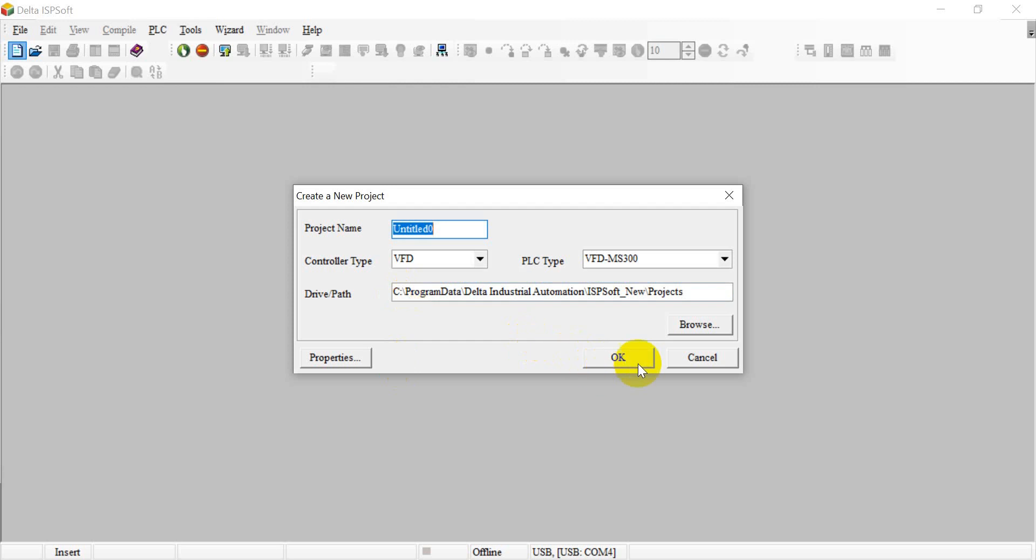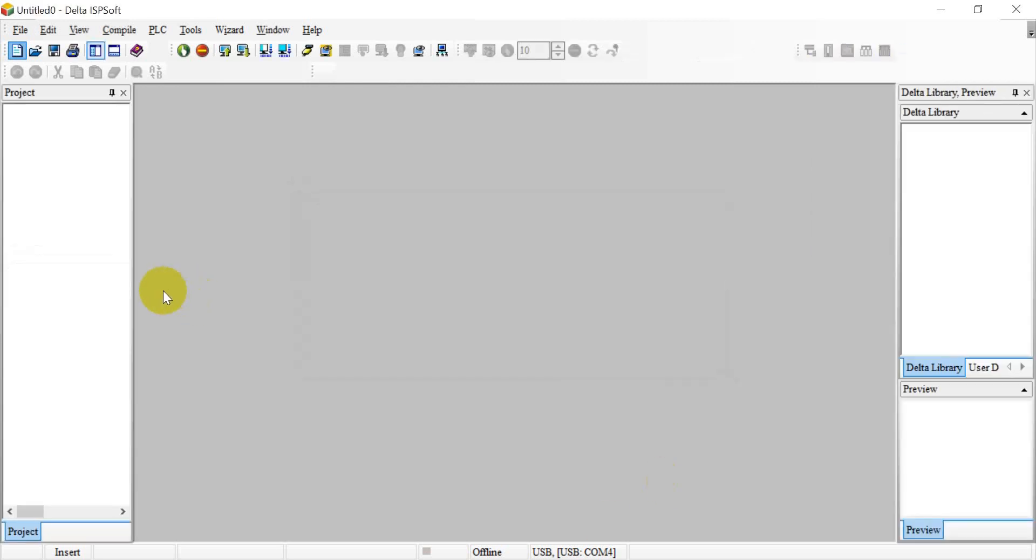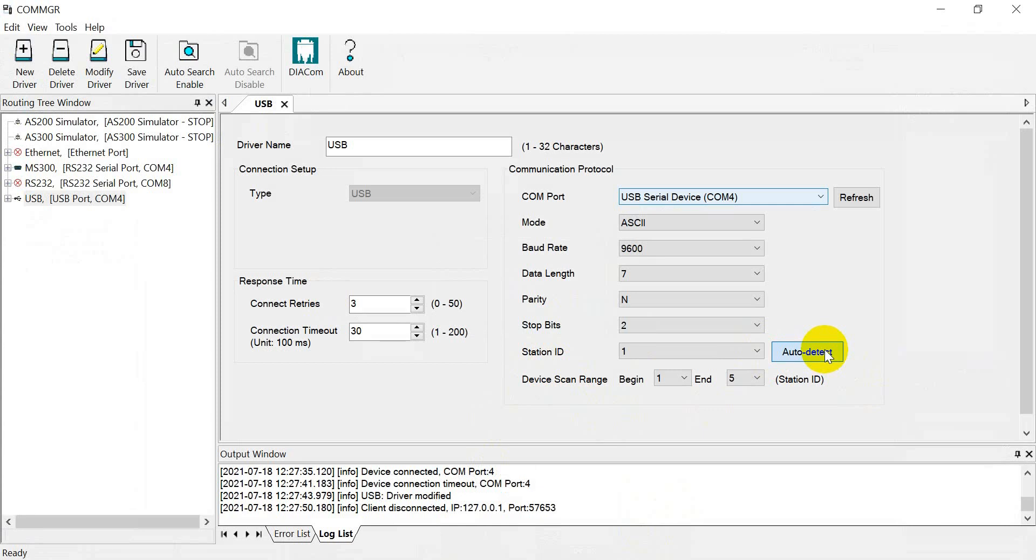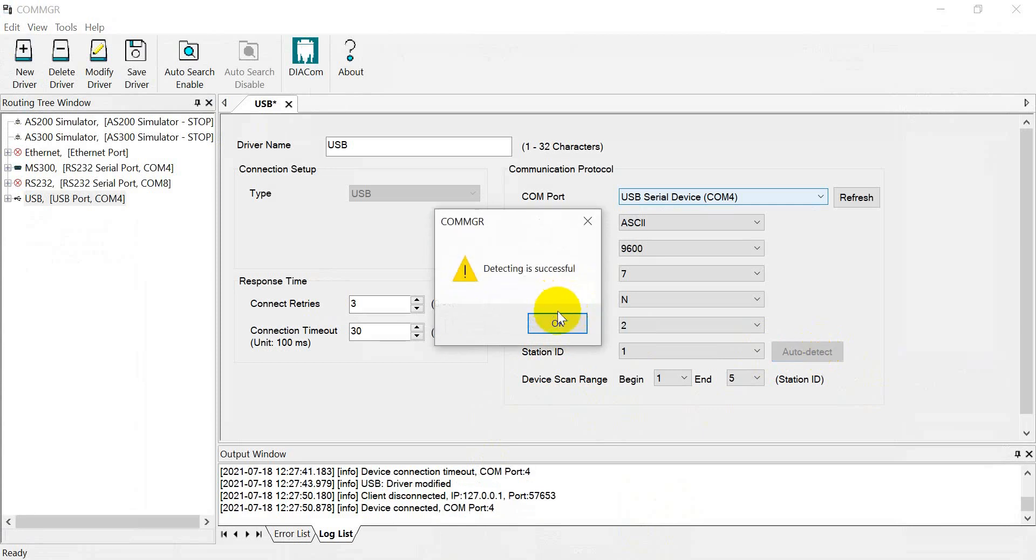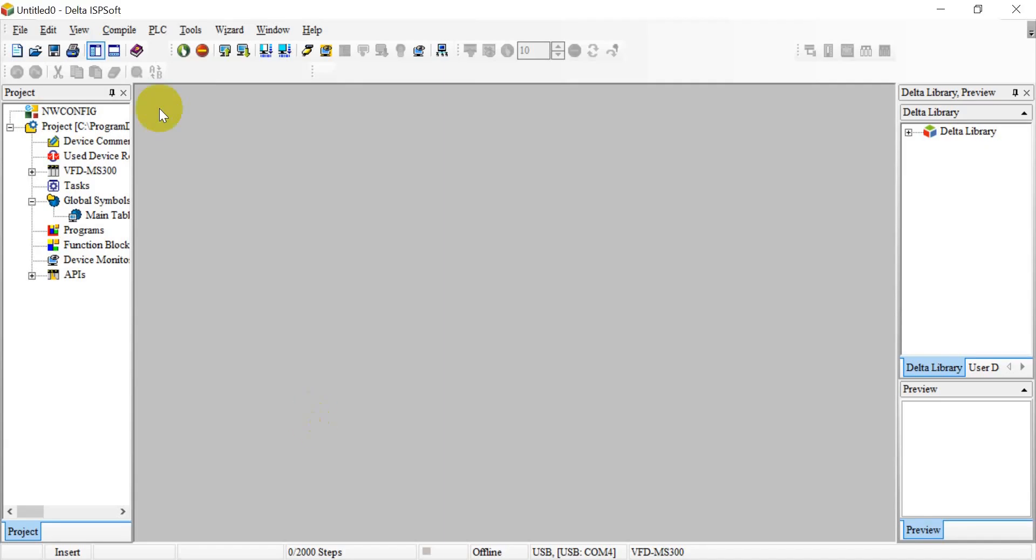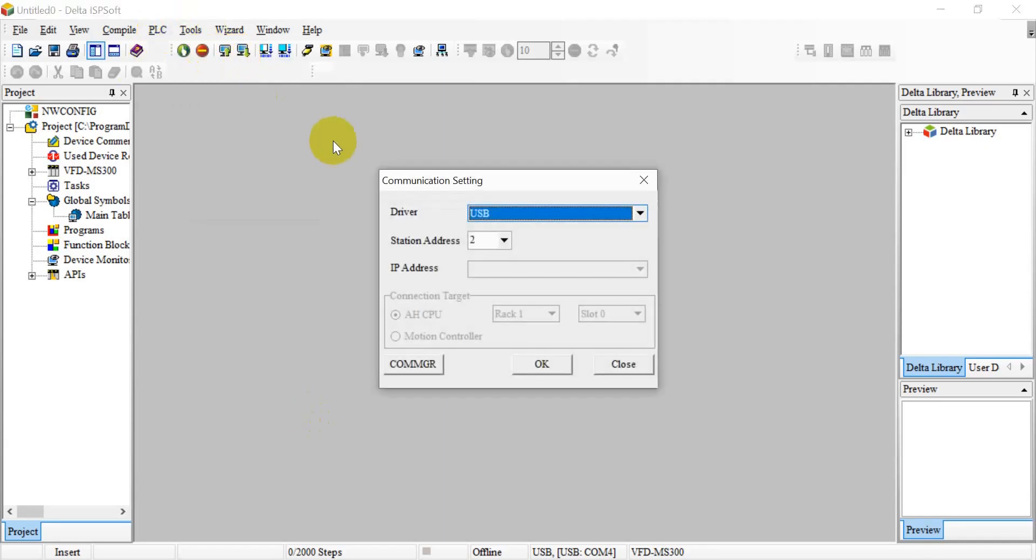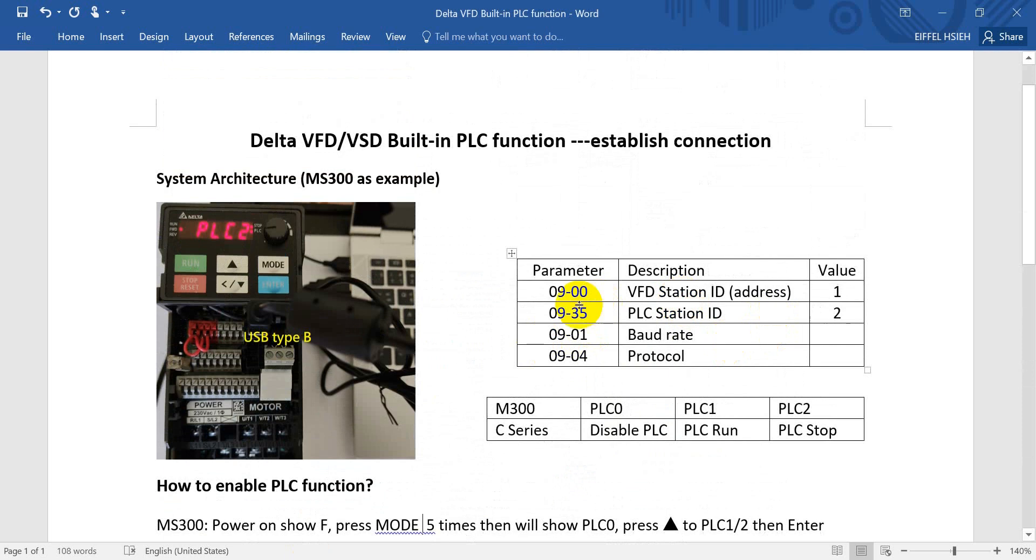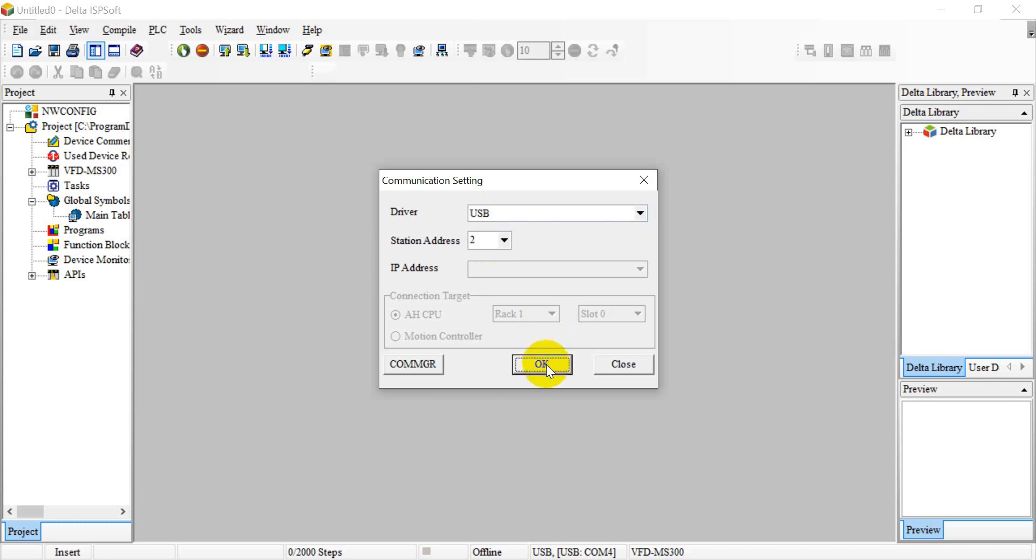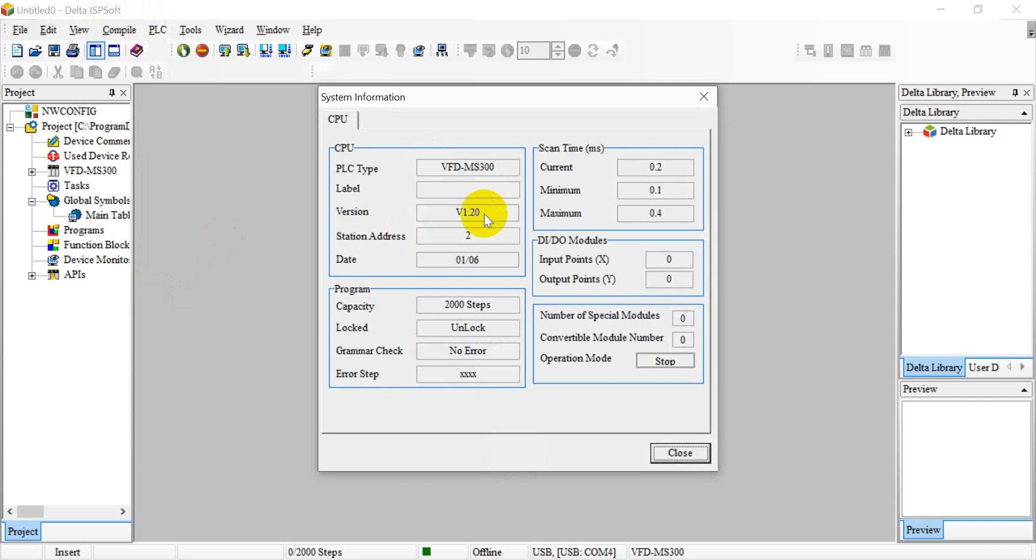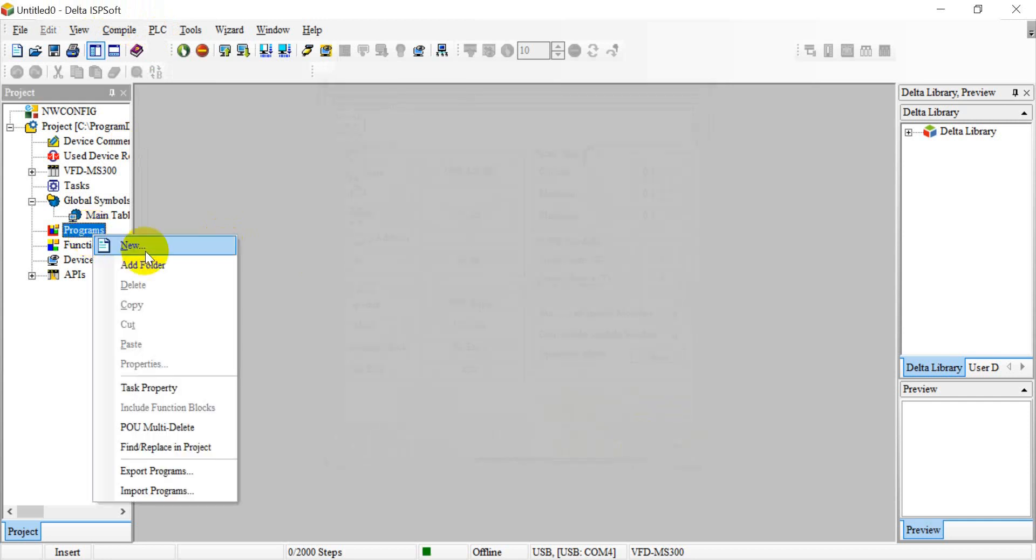Okay, so here I will give you some simple example. Once you see the detecting is successful, then remember to set the driver. And then we can go back to ISP soft. And here, if you still remember, please change the station address to 2. Reason is, 1 means the inverter itself, but today we will use PLC function, so remember change to 2.